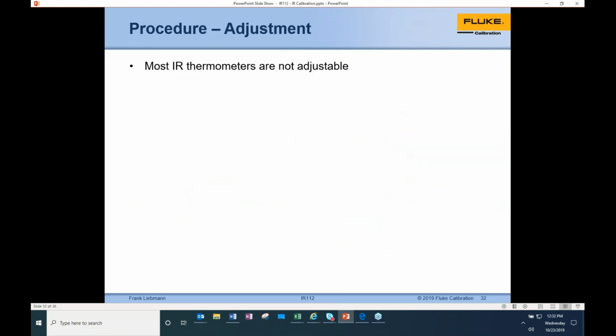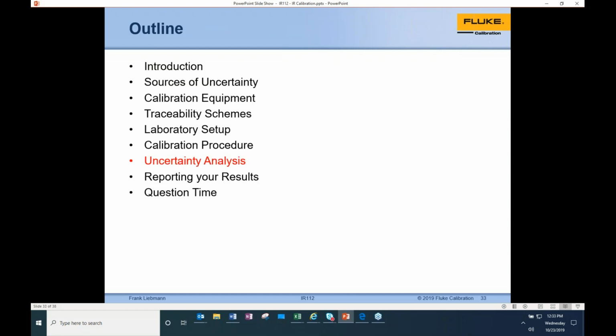Most guns are not adjustable, so usually you check the emissivity. A lot of times when calibrating these, it can just be pass-fail based on tolerance. So again, match it, make sure you're matching emissivity to emissivity. Personally, I haven't adjusted one of these. I know there are some out there that are, but most of the time, from what I see, it requires OEM involvement. They usually have software that they don't hand out, so most of the calibrations I'm seeing done are pass-fail.